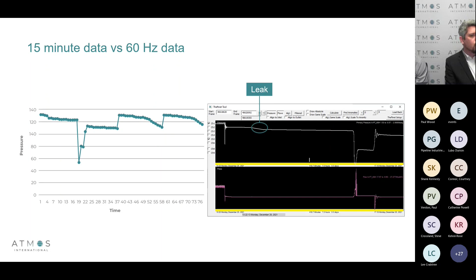But what's being missed in the 15 minute data is the actual start of the leak, which we've highlighted in the green circle. This is being picked up because our system is sampling at that high acquisition rate. So we were able to provide an alarm much earlier than their existing SCADA system would have been able to detect the change, highlighting that you'd be able to detect the leak faster and hopefully reduce the potential risk that this might occur.